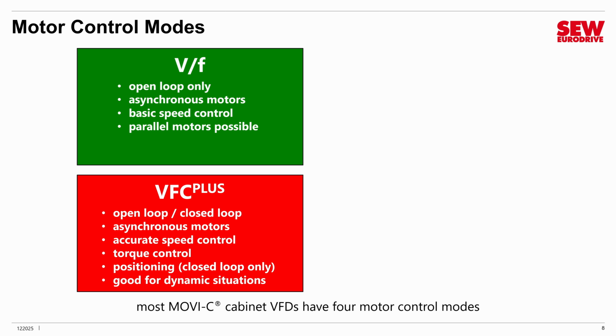But a much better choice is VFC plus mode. VFC stands for voltage flux control. It can be used either open or closed loop. Obviously, you'll get better results with closed loop, but it does a very nice job even open loop. It works with asynchronous motors only. It gives you very accurate speed. It gives you good torque control, and if you have closed loop available, you can do positioning with it. It's also good for dynamic situations where the motor's starting and stopping, changing speed or direction frequently.